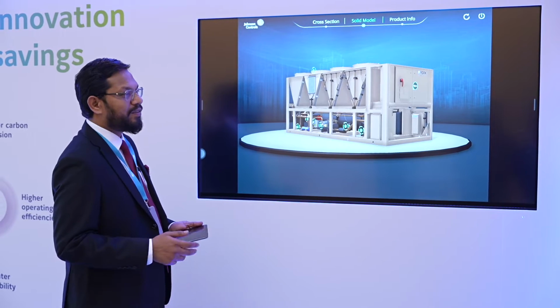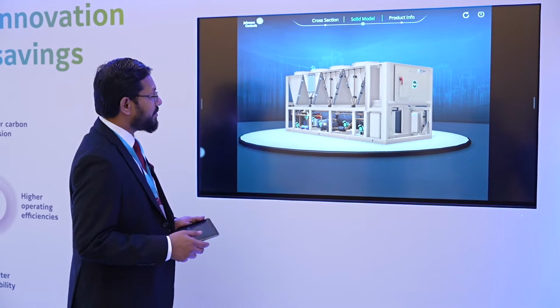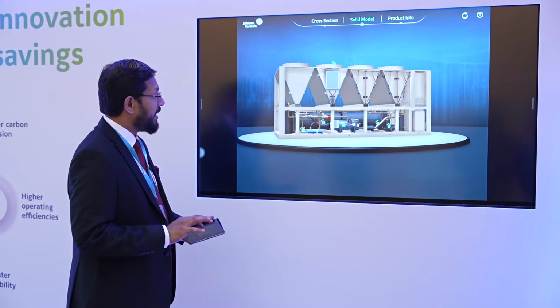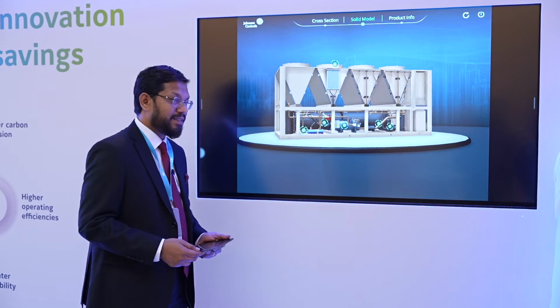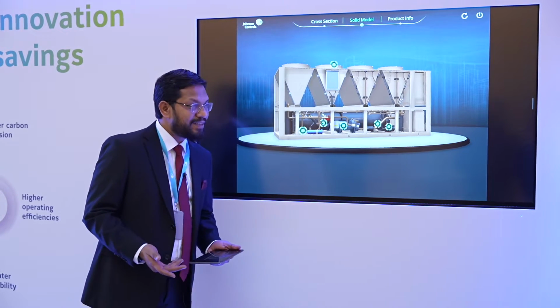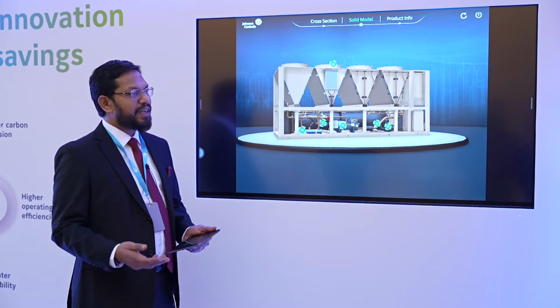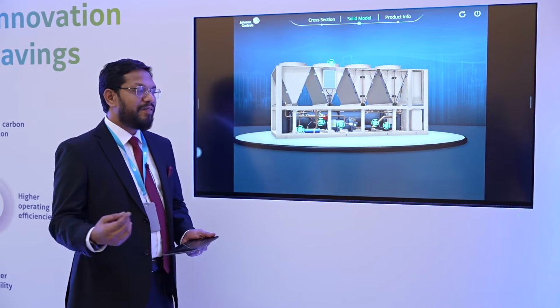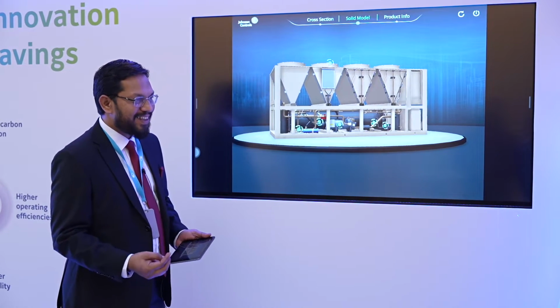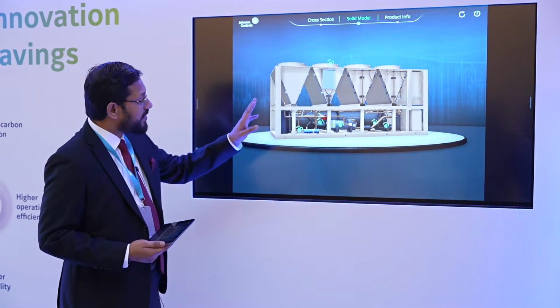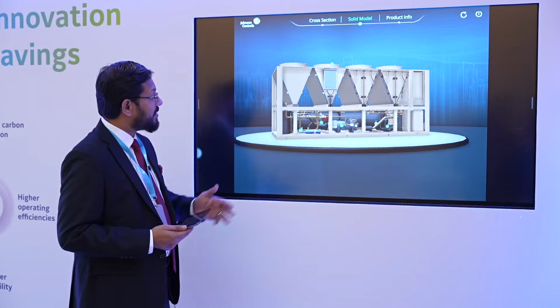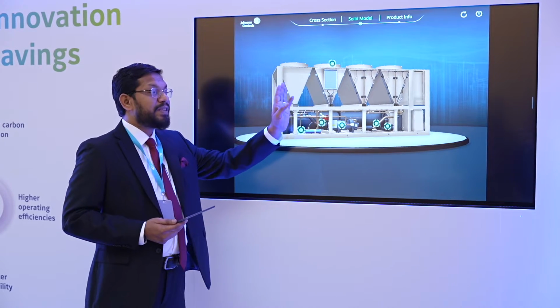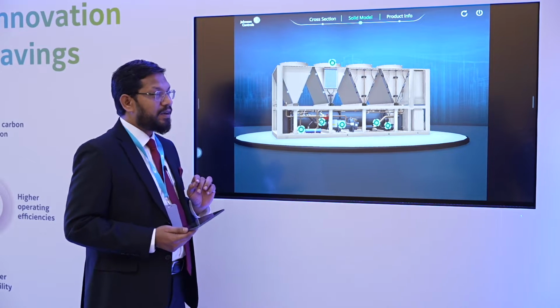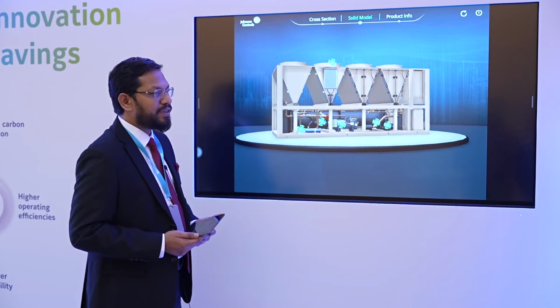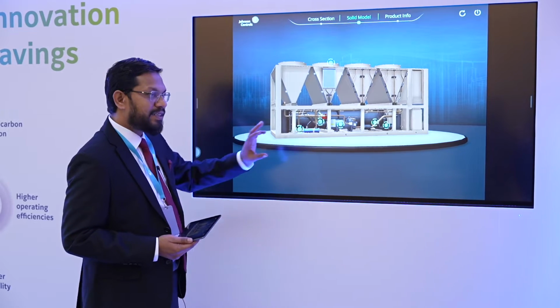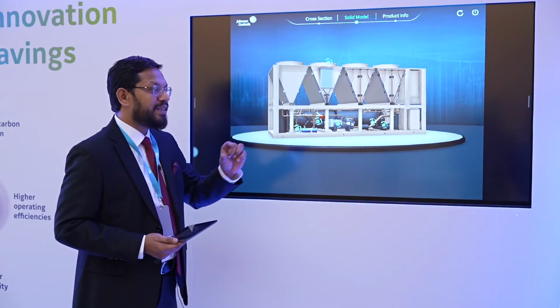If you start right from the condenser by itself, the typical condensers which used to come in an air-cooled chiller used to be copper aluminum condensers. The copper aluminum condensers have two different metals, so they always tend to have galvanic corrosion when you put them into an environment, and oxidation happens between the two different metals, so they start corroding each other. That's why we introduced in these chillers a V design on the condenser coils, where you can see here. These are made with a single material, called microchannel condenser coils. We introduced them into the air-cooled chillers back in 2010. This is again an innovation even at the component level of the chillers.